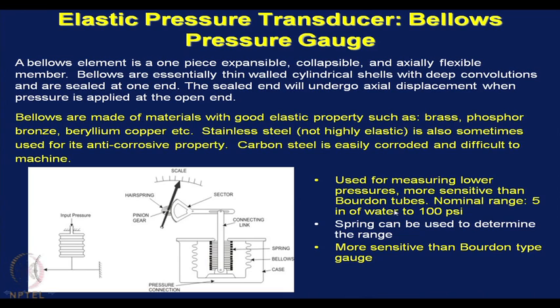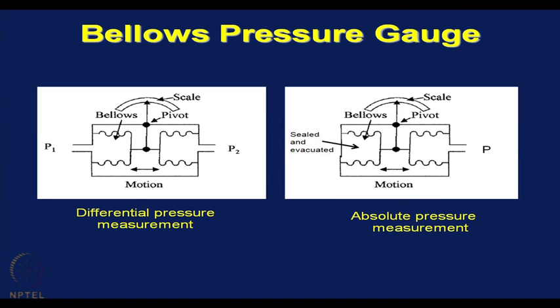Bellows elements are used for measuring lower pressure. It is more sensitive than Bourdon tubes. The nominal range over which a bellows element can be used is about 5 inch of water to about 100 psi. Bellows pressure gauge can be used to measure gauge pressure, differential pressure as well as absolute pressure.